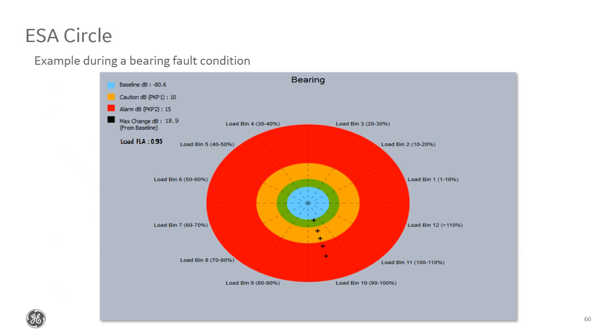There was another question, and I know the historical records capture data every 15 minutes. How often does the ESA actually do calculation? I believe the ESA calculation is done every 1 minute. Okay. So if you actually had this ESA circle diagram open, for example, you would see it refresh every 1 minute with the updated information. So the actual calculation is done every 1 minute, and then the historical log averages all of those samples over the 15 minutes, and stores it in a log every 15 minutes.